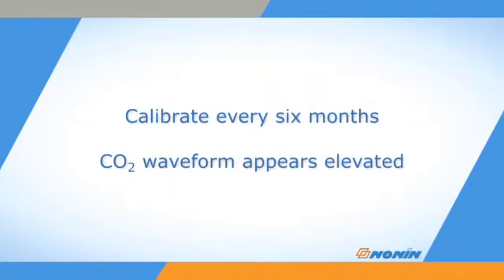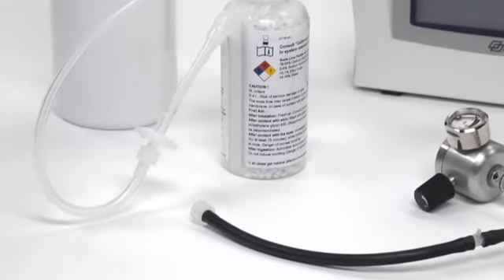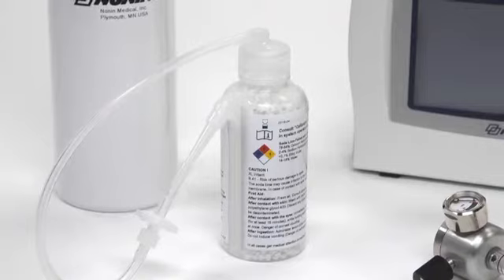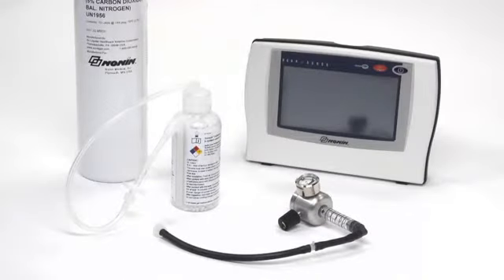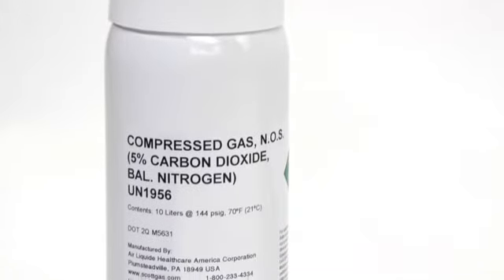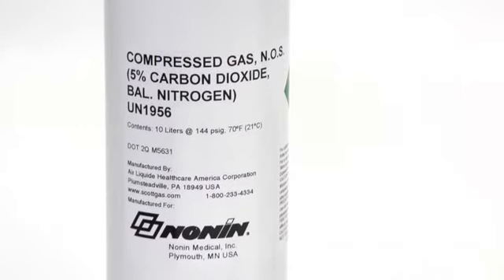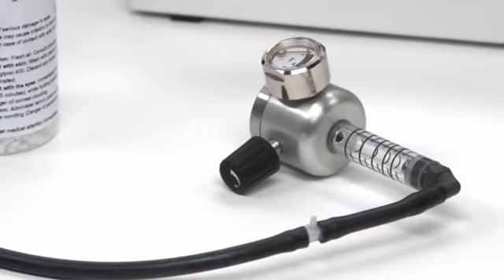RespSense and LifeSense capnography functions should be recalibrated every 6 months, or if the CO2 waveform appears elevated. The pulse oximetry functions of the LifeSense monitor do not require calibration. Calibration is typically performed with a calibration apparatus available from NONIN Medical. If you do not have a calibration apparatus available, you may follow the same procedure to calibrate the monitor with ambient air. 5% CO2 verification gas and a sampling valve are also available from NONIN Medical. These may be used at any time to verify your monitor is in calibration.